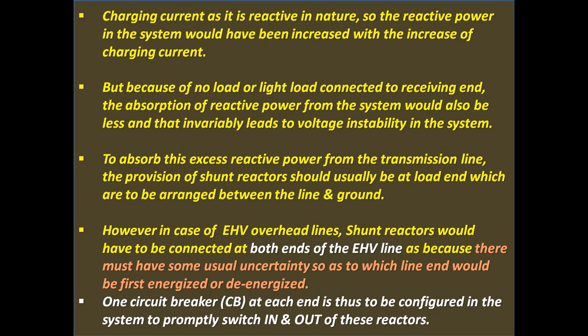However, in case of extra high voltage overhead lines, shunt reactors have to be connected at both ends of the EHV line, because there is usual uncertainty as to which line end would be first energized or de-energized. One circuit breaker at each end is thus configured in the system to promptly switch these reactors in and out.